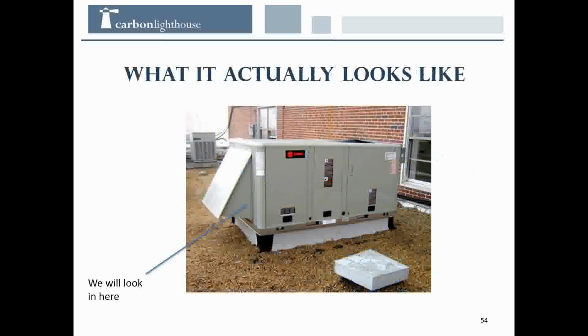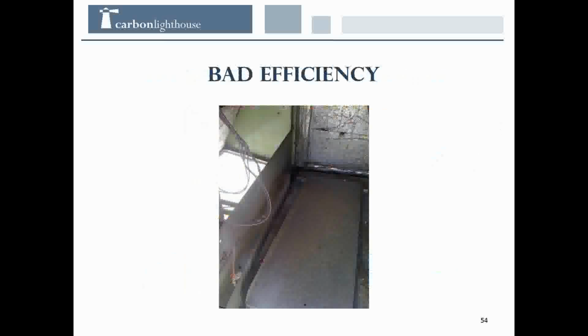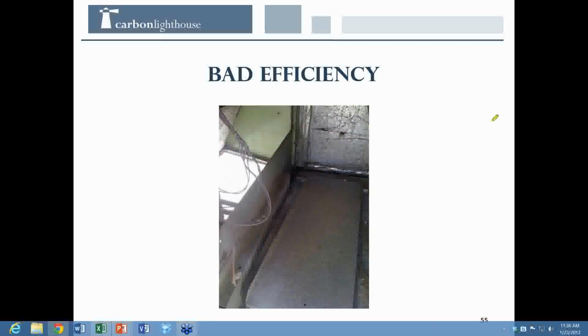A really, really bad energy efficiency project looks something like this. There's a bunch of control wires dangling, not connected to anything. This is just a hole, there should in fact be a damper there, not just a hole. That damper turns out to be lying on the ground here, preventing any return air from coming into the building. So at least in this case, this economizer, that's what this part is called, has failed in a way that's not dangerous to occupants, since there is still fresh air coming into the building.